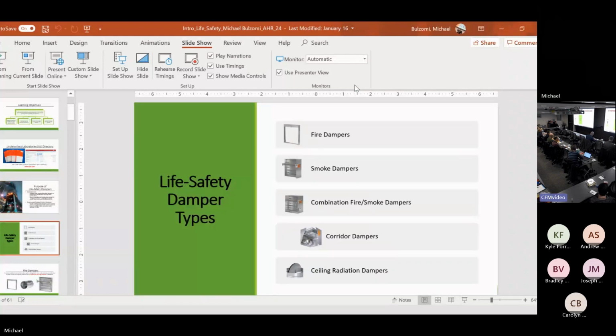These are different types of life safety dampers. You have fire dampers, smoke dampers, combination fire smoke dampers, and ceiling radiation dampers. This corridor damper, that's a type of combination fire smoke damper. So it goes through the same testing as a fire smoke damper, but California Building Code requires in hospitals, in egress corridors for hospitals, you must have a 1 hour corridor rating to your fire smoke damper. So it undergoes additional testing to get that rating. Again, it's a California Building Code requirement.